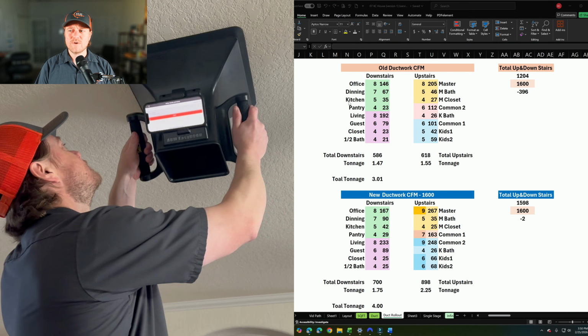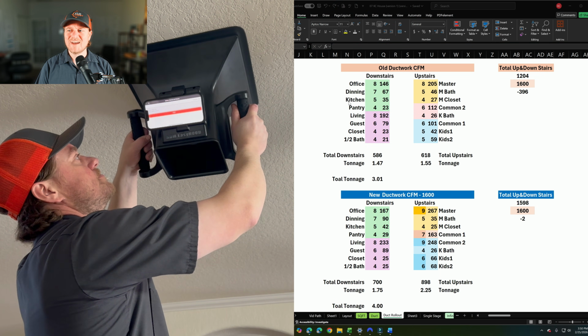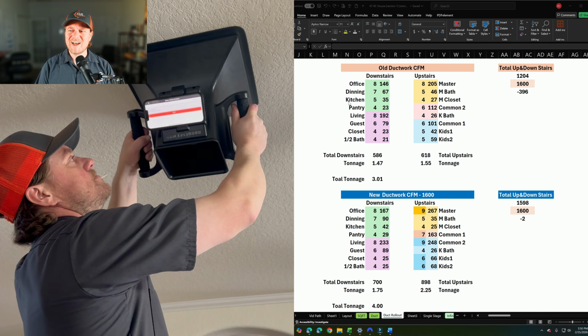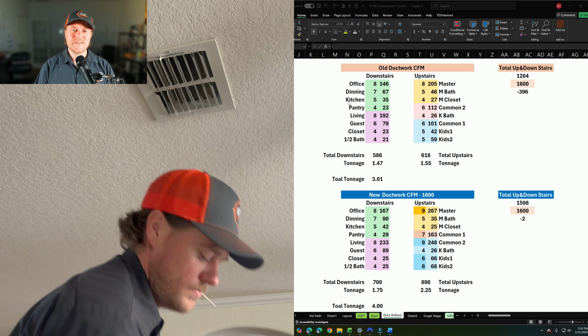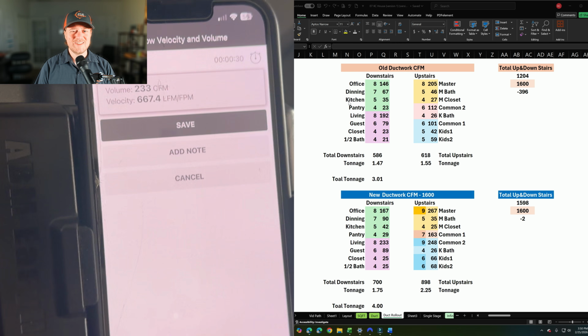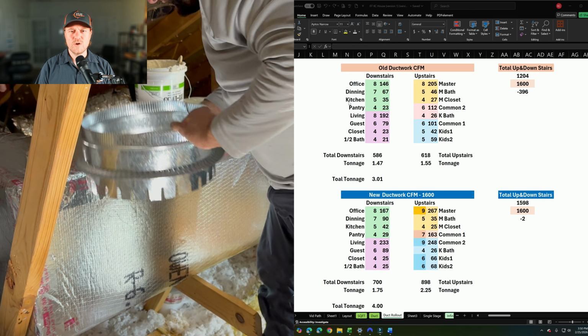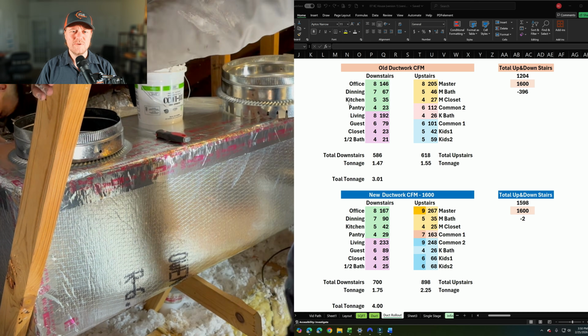The total airflow that we're getting is 1598 CFM, almost exactly 1600 CFM. In the last test that we did, it was almost exactly 1400 CFM. Whenever I see things this close, I always think to myself, this person is full of crap because nothing is ever perfect. Now I might be splitting hairs here.